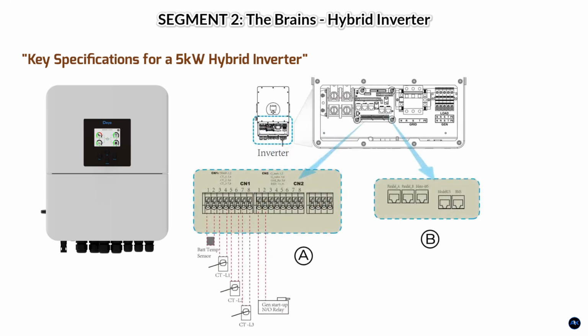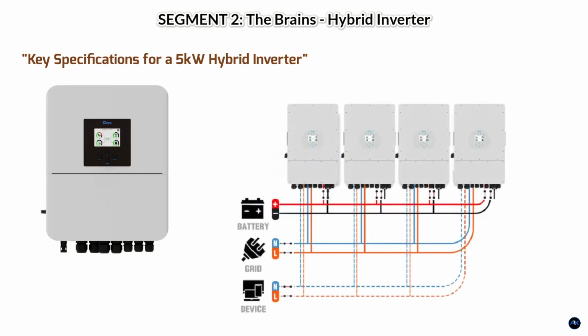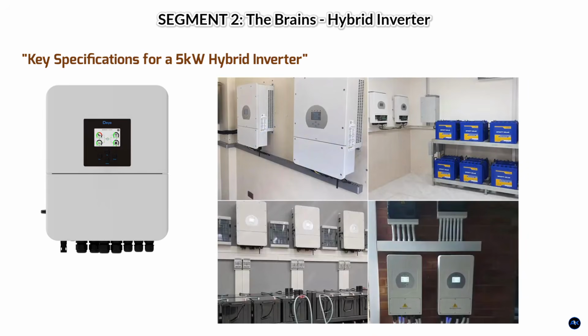Communication ports. For monitoring: Wi-Fi, Bluetooth and RS-485, and often for communication with smart batteries. Parallel functionality. Some inverters allow multiple units to be connected in parallel for future expansion, increasing total power output. Inverter placement. Choose a cool, dry, well-ventilated area, ideally close to your main electrical panel and batteries to minimize cable runs. Ensure it's easily accessible for monitoring and maintenance.